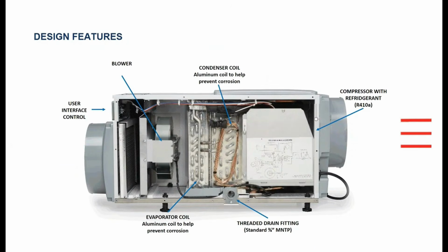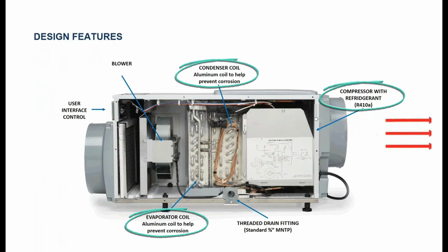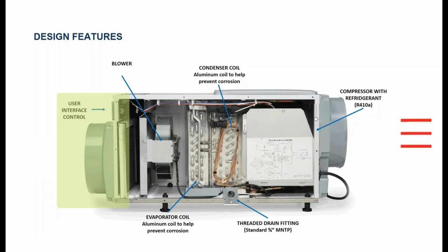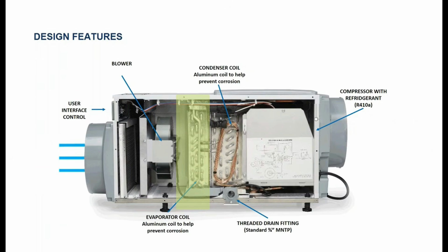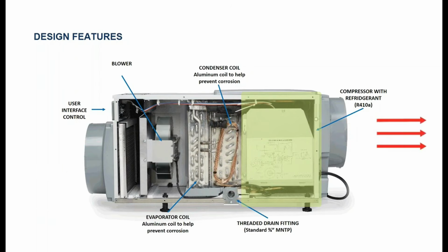So how does a whole home dehumidifier work? It's basically a small self-contained refrigeration unit that ties directly into your central ductwork. And much like your central AC system, it has a compressor, a condensing coil, an evap coil, and a blower. So the way that these units dehumidify the air is it first chills the air, and then from there it warms it back up. So when air first comes into the unit, it's going to meet the cold evaporator coil. From there, it's going to pass through the warm condensing coils and then over the compressor. And in this process, it's pulling the maximum amount of humidity out of the air.